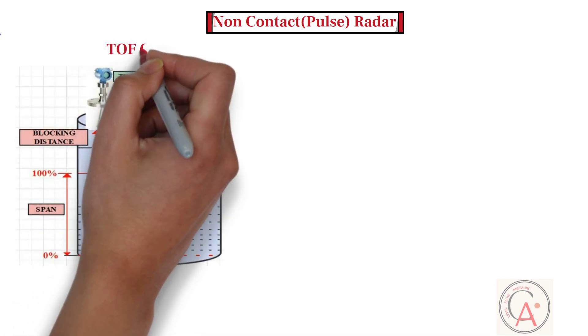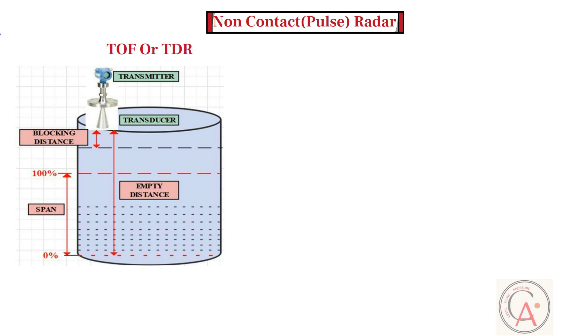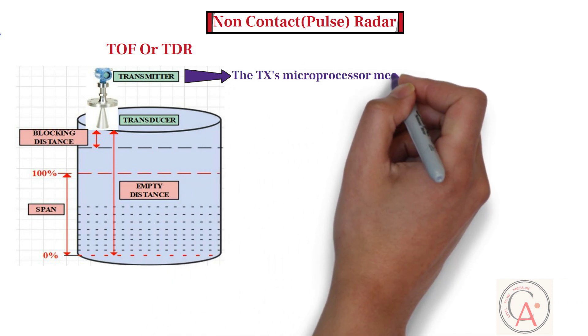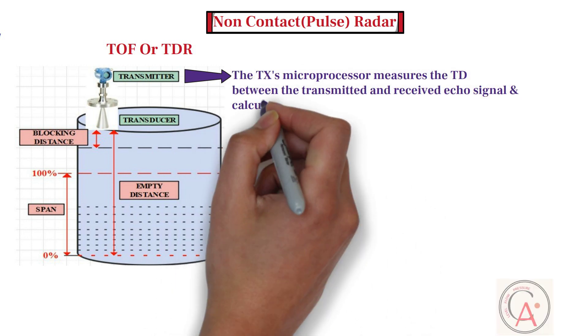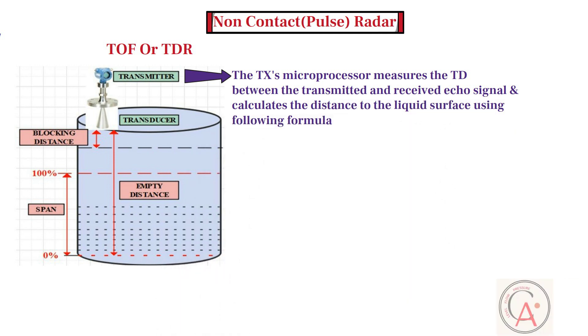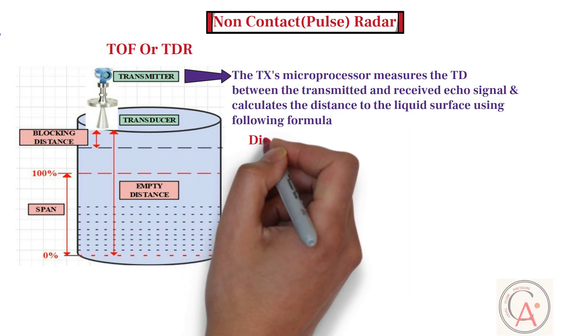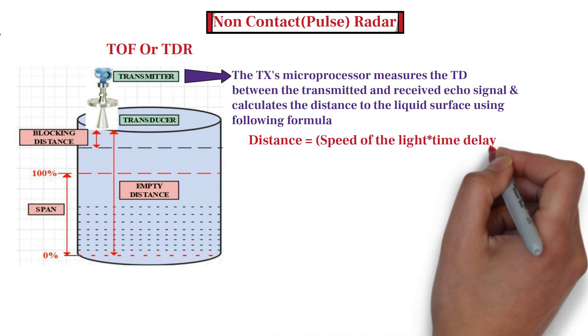Now I'm going to explain how non-contact type radar level transmitters work. Non-contact type radar level transmitters work on the time of flight measuring principle, also known as time domain reflectometry. This type of transmitter sends high-frequency radar pulses traveling at the speed of light towards the bottom of the tank, which bounce off the product's surface and return to the sensor. The transmitter's microprocessor measures the time delay between the transmitted and received echo signal and calculates the distance to the liquid surface using the formula: Distance = (Speed of Light × Time Delay) / 2.